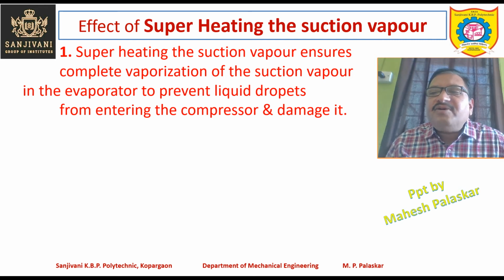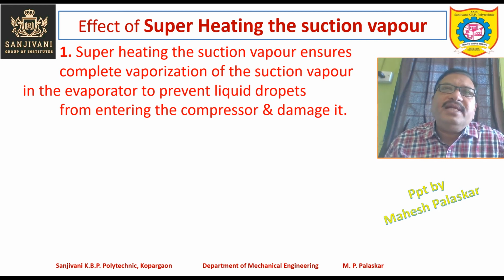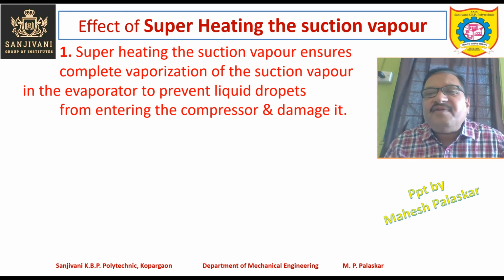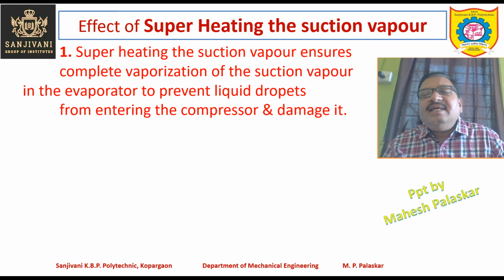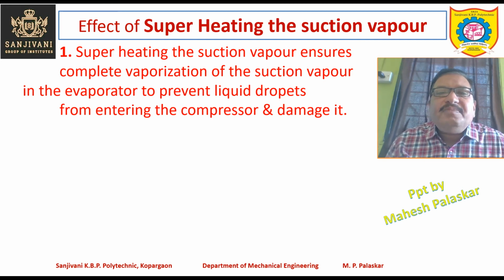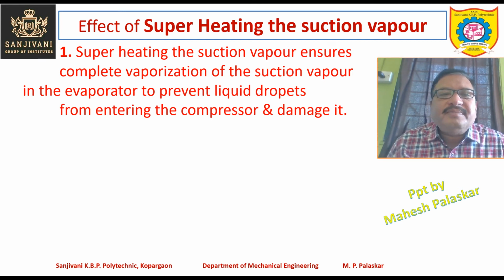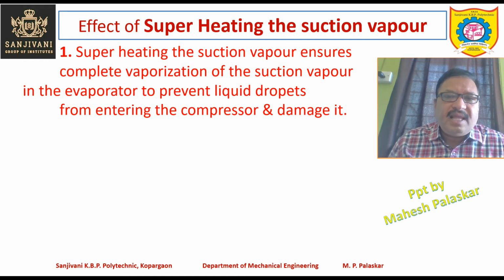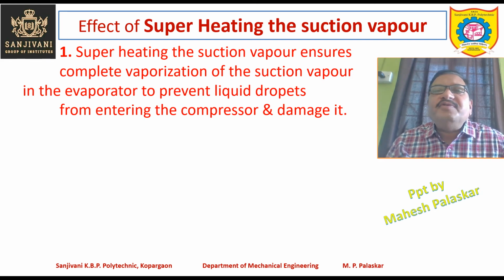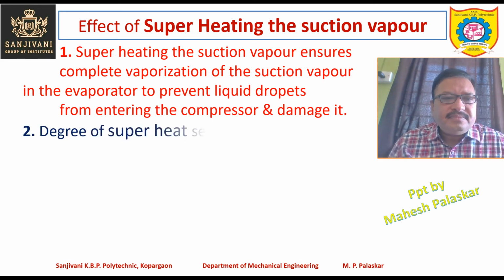So the liquid droplets damage the compressor, and therefore we must avoid the liquid droplets entering the compressor, and for that we have to ensure that the complete vaporization of the suction vapor takes place before this vapor enters the compressor. And that is the main purpose or the main advantage of superheating the suction vapor.